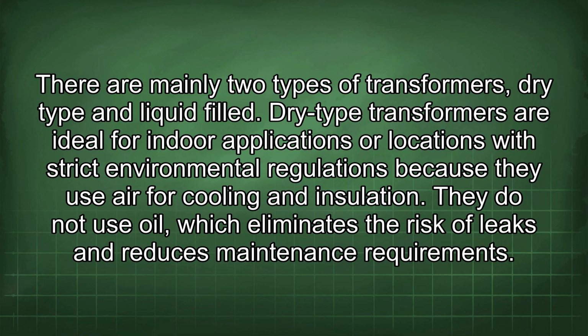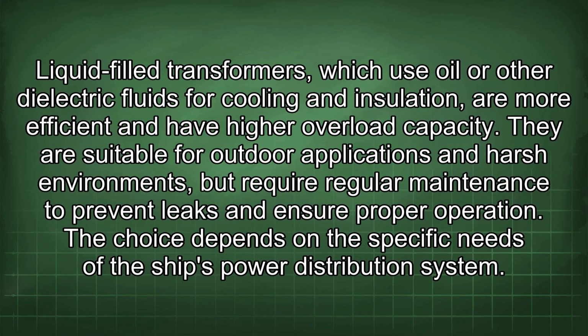Dry-type transformers are ideal for indoor applications or locations with strict environmental regulations because they use air for cooling and insulation. They do not use oil, which eliminates the risk of leaks and reduces maintenance requirements. Liquid-filled transformers, which use oil or other dielectric fluids for cooling and insulation, are more efficient and have higher overload capacity. They are suitable for outdoor applications and harsh environments, but require regular maintenance to prevent leaks and ensure proper operation. The choice depends on the specific needs of the ship's power distribution system.